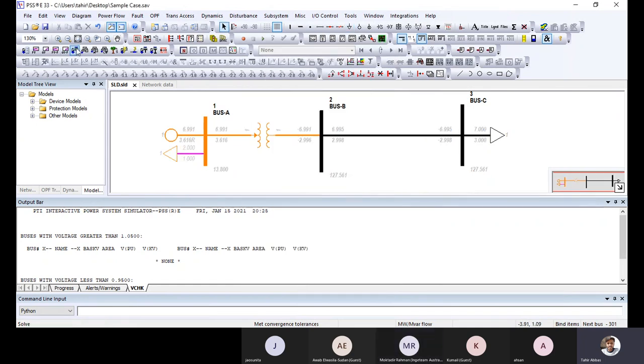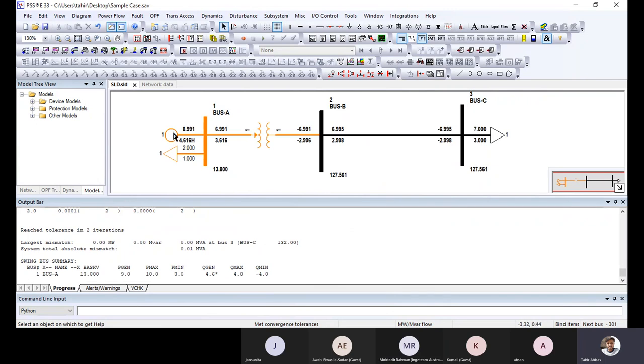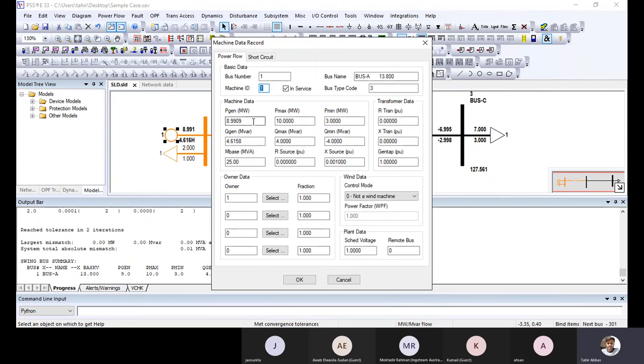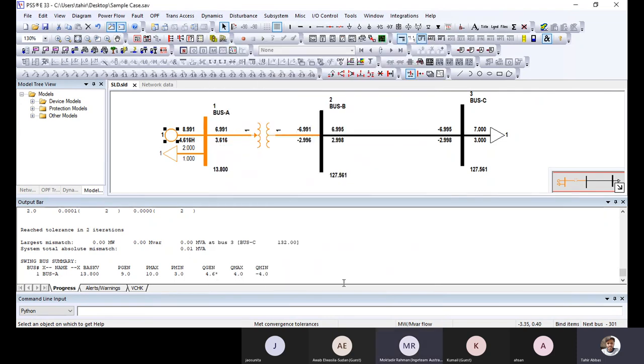So now I'm solving the case again. Now you can see that 8 megawatt is generated here, with 2 megawatt going to the auxiliary load and 6 coming out again here, because this is a swing generator, and it is now generating 8. Otherwise, with another generator, only the swing can adjust its generation, but all other generation is fixed. So basically, this is the megawatt that is given on the nameplate data of a generator.